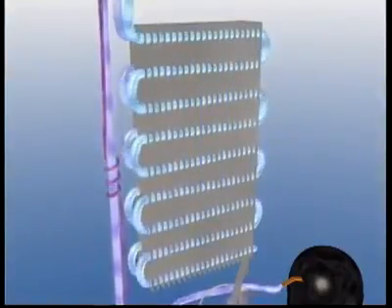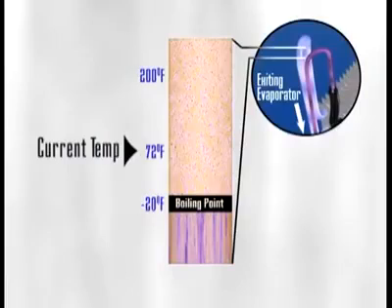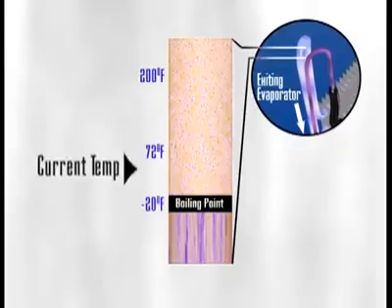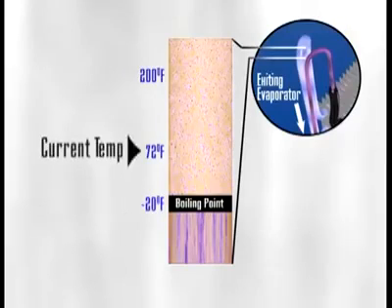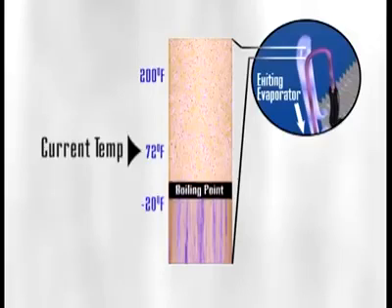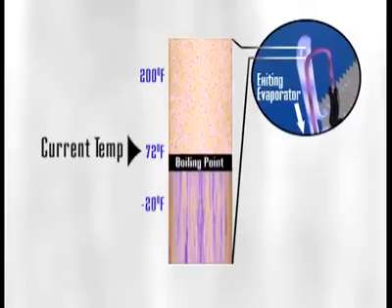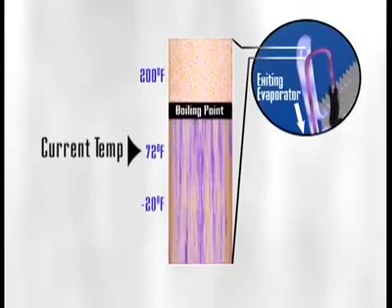The refrigerant, on the other hand, is of no use unless it can be converted back to a liquid so that it can change phase to a gas again, absorbing more heat. To convert it back to a liquid, we must either lower its temperature below its boiling point or raise its boiling point above its temperature. Since we can't lower its temperature all the way to -20, we temporarily raise its boiling point by increasing the pressure.